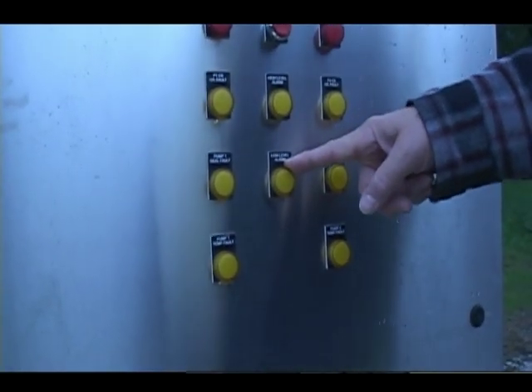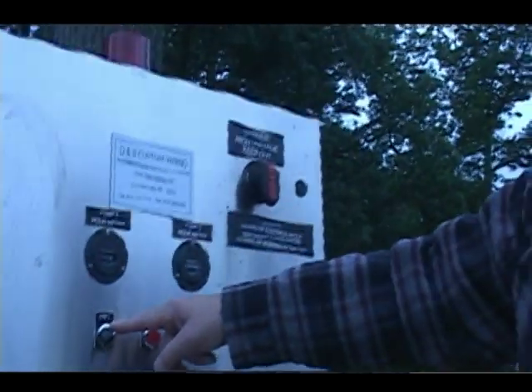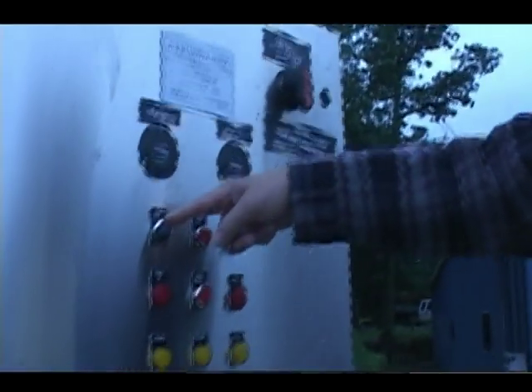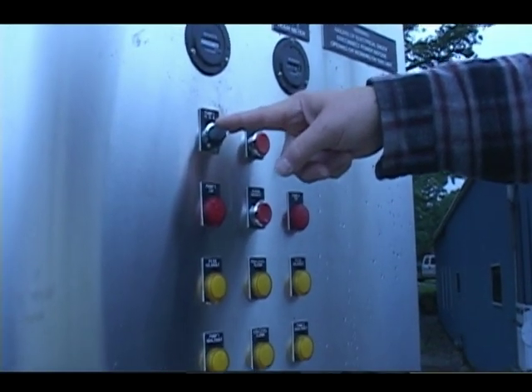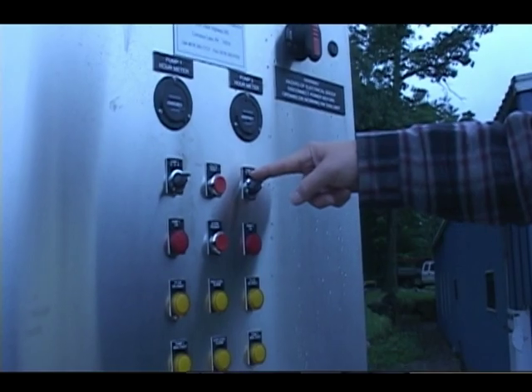Normally you would have the pump in the automatic mode, which means as the level in the wet well fills, it'll come up to the pump on level, which is the third float, and turn on the lead pump. It'll go down to the pump off level, which is the second float, and shut the pump off. On the next cycle, the other pump will turn on.